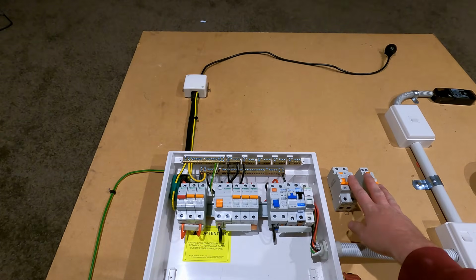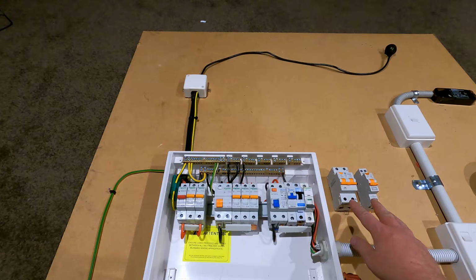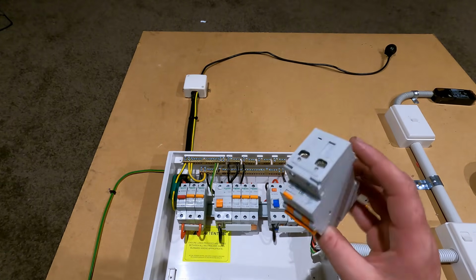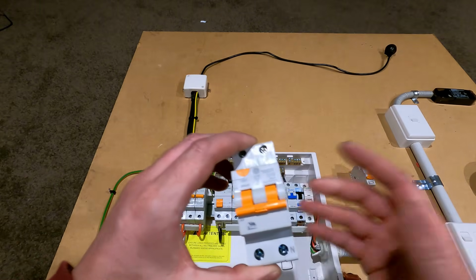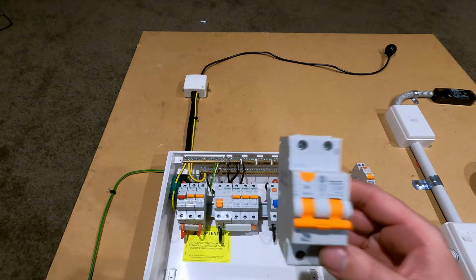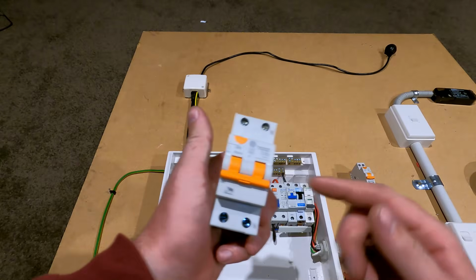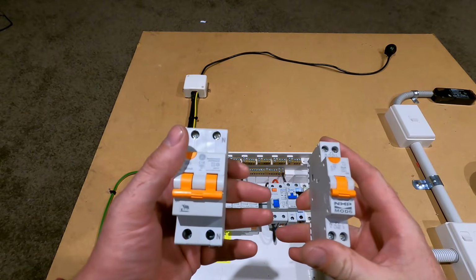So over to the side here, I've got a couple of RCBOs. Now these are residual current devices with overcurrent protection, so they work as an RCD and as a circuit breaker all in one. This one here is a 2-pole. And this one here is a 1-pole. As you can see, it just takes up one slot.